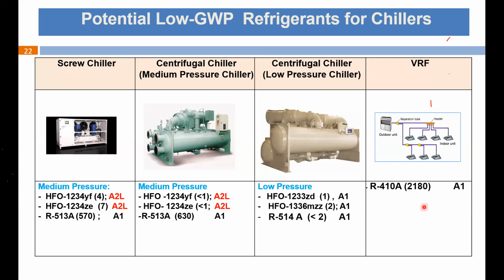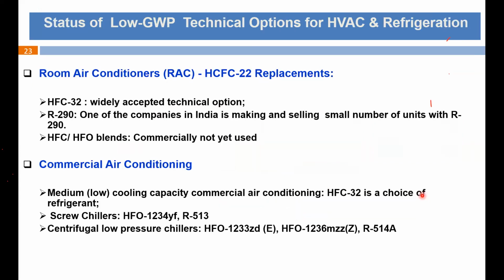But for VRF systems, we still don't have any option other than R410A, which has a very high GWP. To summarize, R32 is the widely acceptable technical option for room aircon. R290 is being used by some manufacturers. Blends of HFC and HFO are still not commercially used for room aircon. For commercial air conditioning, medium cooling capacity systems like ductable packages, R32 is a choice. For screw chillers, as I told you, HFO refrigerant is already launched by some manufacturers, as well as R513A. For low pressure centrifugal chillers, these HFO refrigerants are already launched by some manufacturers.